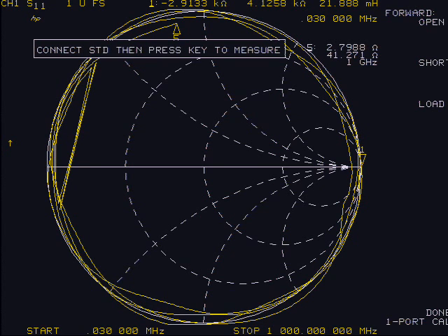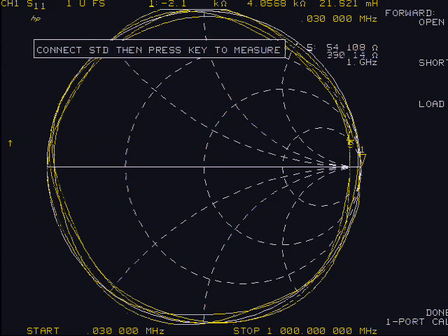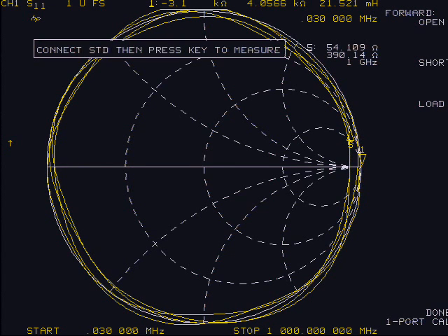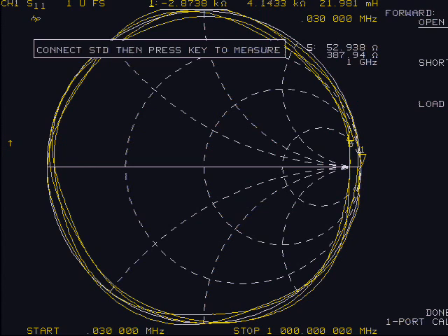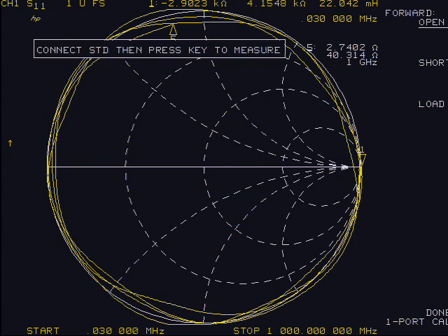To speed things up, we will use the GR or General Radio connectors as they slip or push on quickly. But other calibration connector sets are available, including Type-N, SMA, and APC or Precision 7mm.